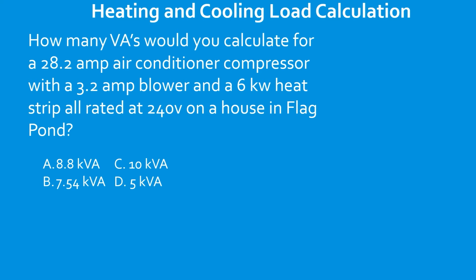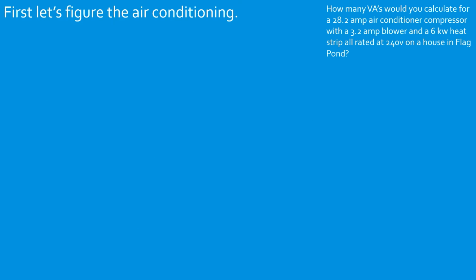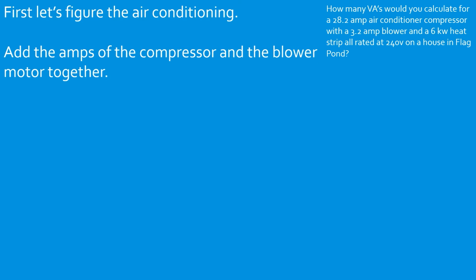Great job. How many VAs would you calculate for a 28.2 amp air compressor with a 3.2 amp blower and a 6 kW heat strip, all rated at 240 volts at a house in Flag Pond? All right, so we're going to use the larger of the two. So first, let's calculate the air conditioning. We're going to add the amps of the compressor and the blower motor together. That's going to give us 31.4 amps.